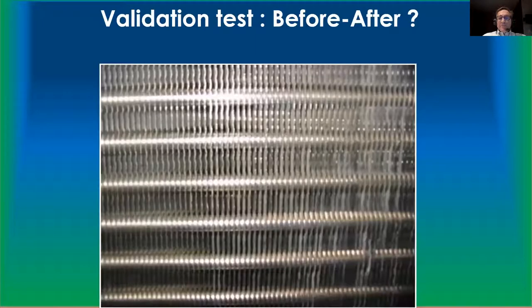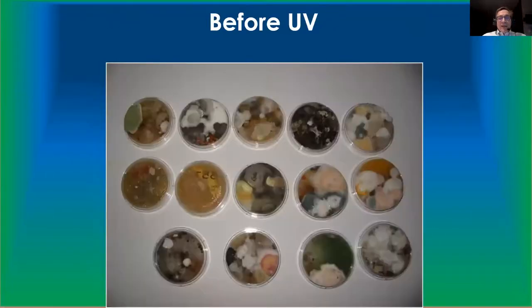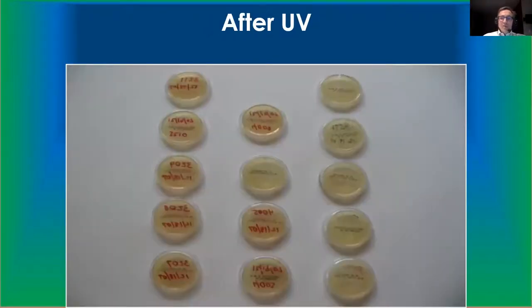Here's a typical coil. Before treatment, that's again the before, and that's the after. So that's a way to verify. You can also verify the intensity on the coil using a UV meter to make sure that your minimum point, say, is above 250, and make sure typically it's in the corners or somewhere like that you have the lowest level, but it will work its way through and you will be able to verify after installing the UV lights.